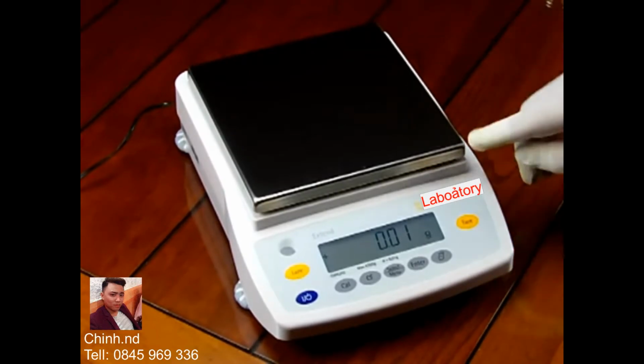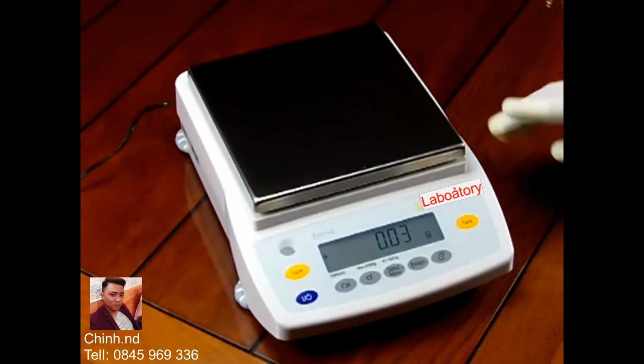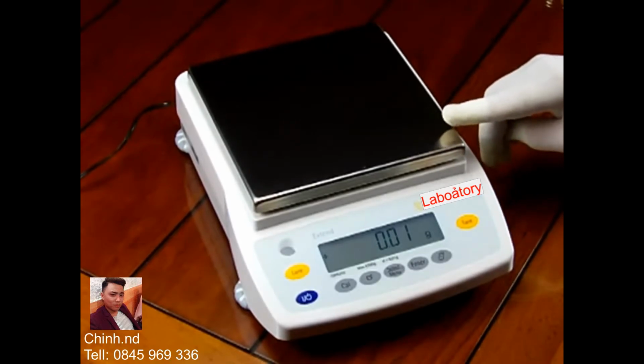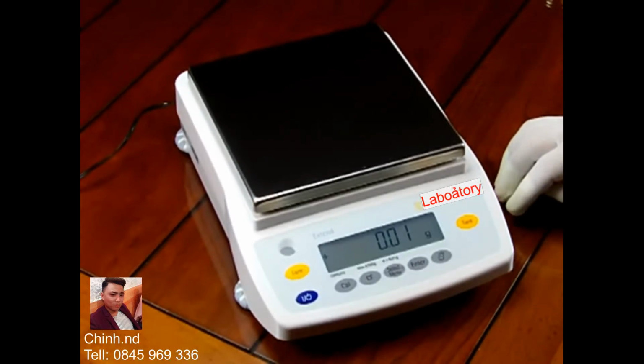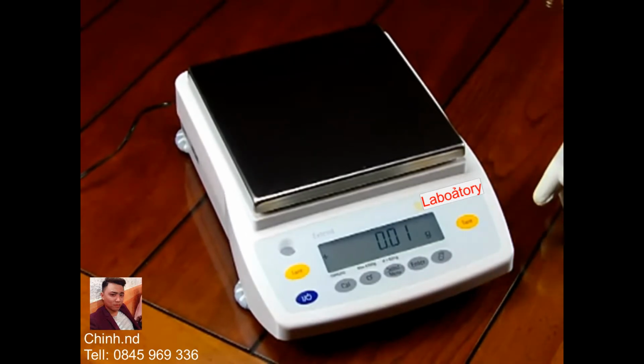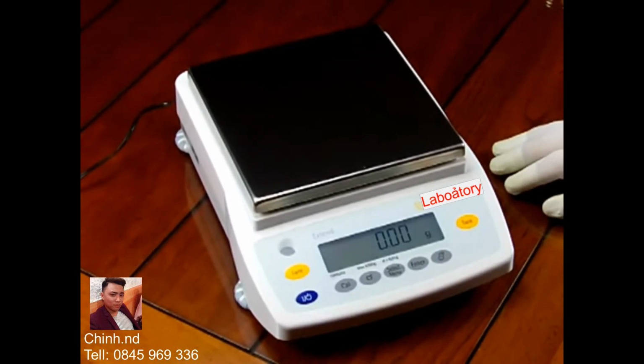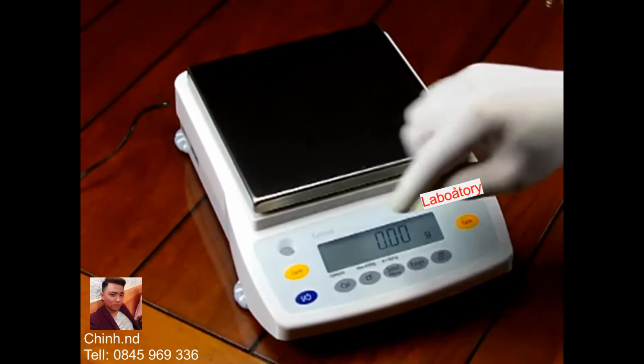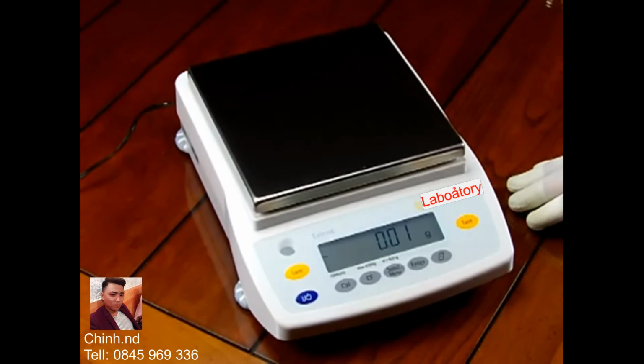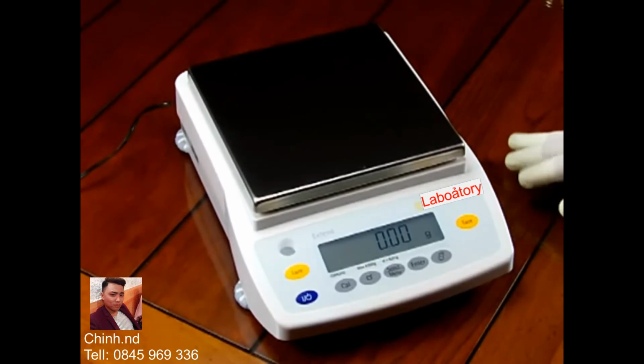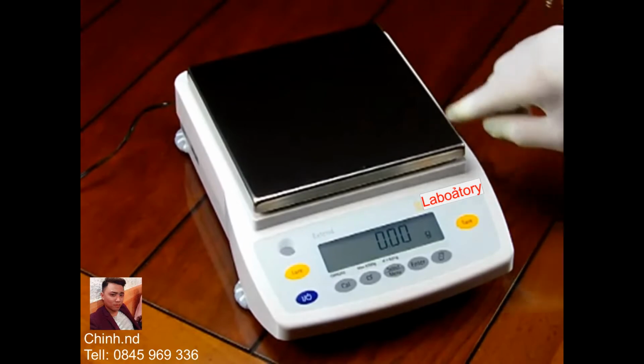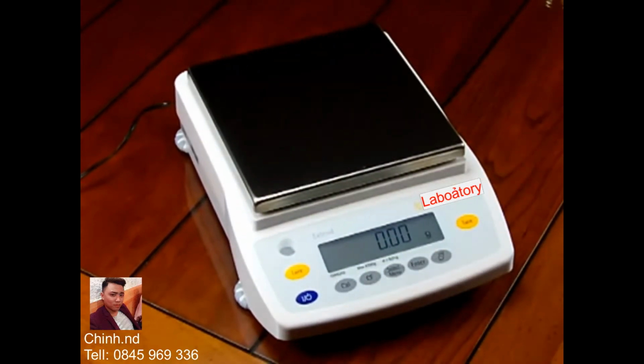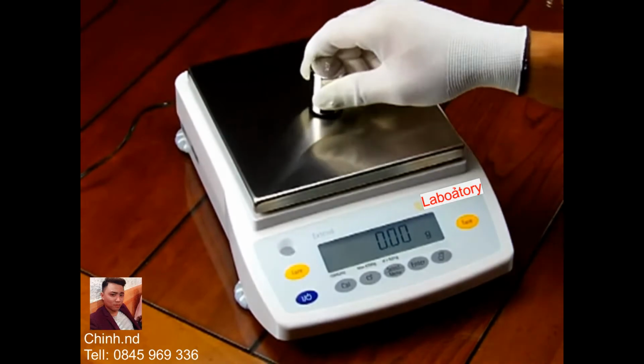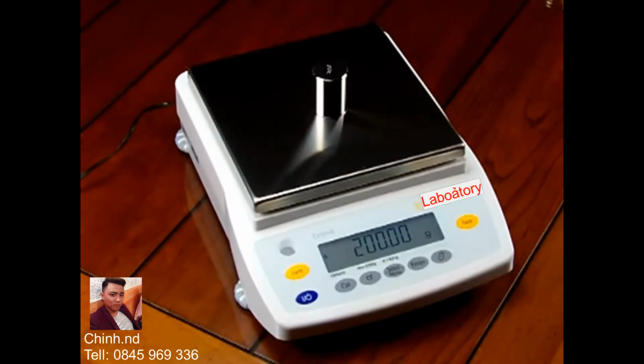So having that windshield also, if you had a large object that you were weighing, if that object was going over the side, it could touch that windshield and interfere with the actual weight of the widget on the platform. The other thing is, if you ever have a spill, we don't recommend spilling anything on a balance, but if you did, if you had that windshield around the edge, it would contain that liquid on the balance. So Sartorius is the premier manufacturer, and again, there's no windshield, just weigh-in platform, and that's because Sartorius knows how to build a balance and give you spectacular weigh-in results.